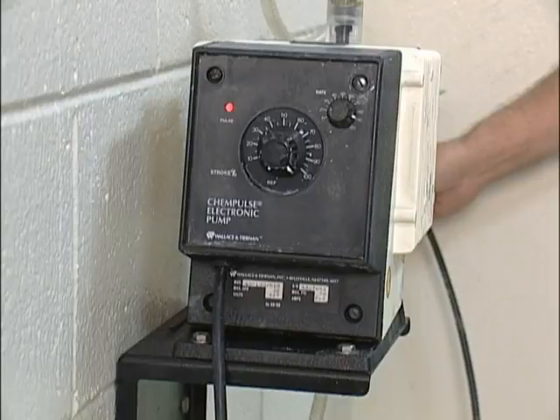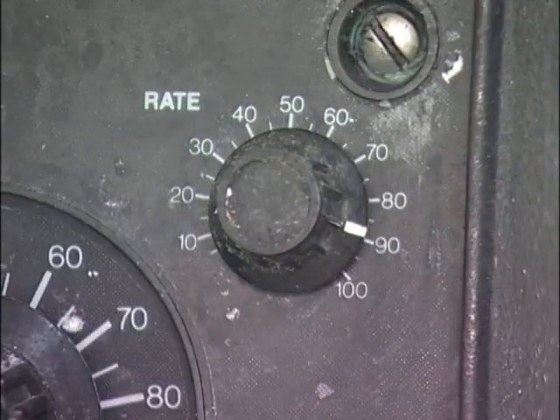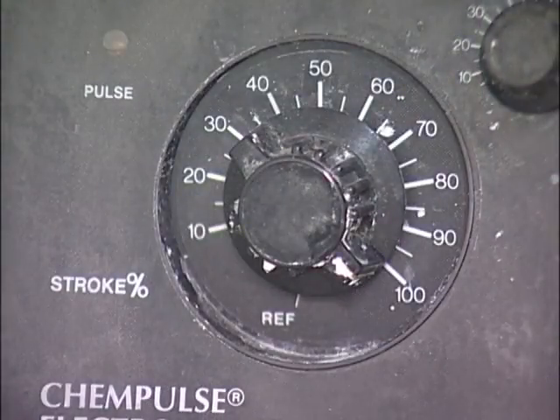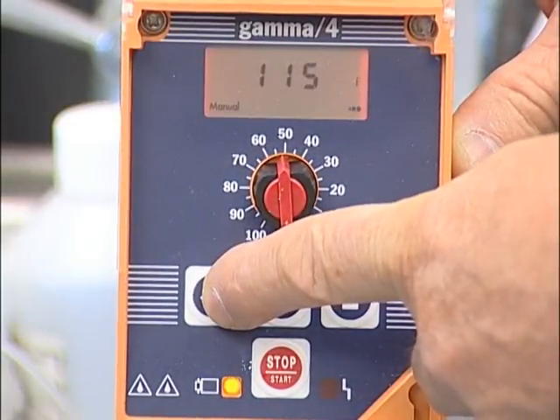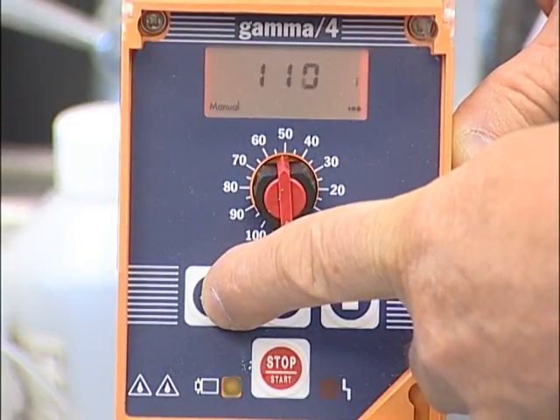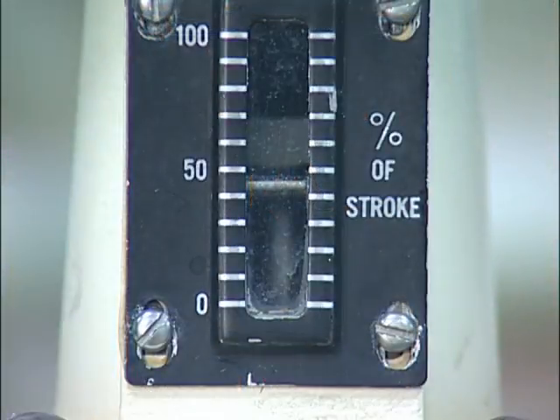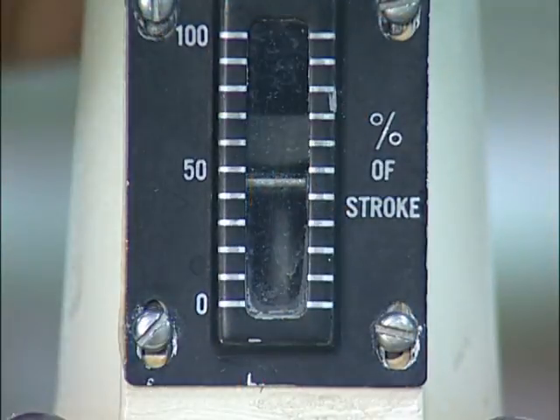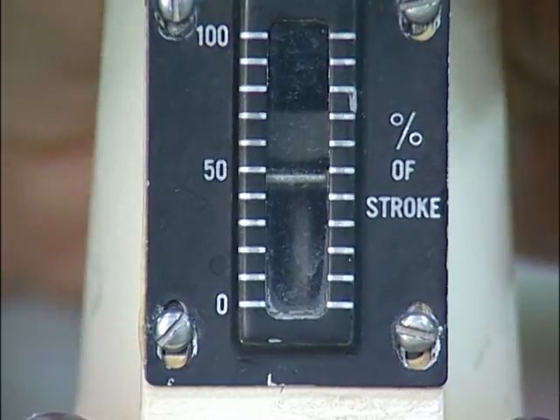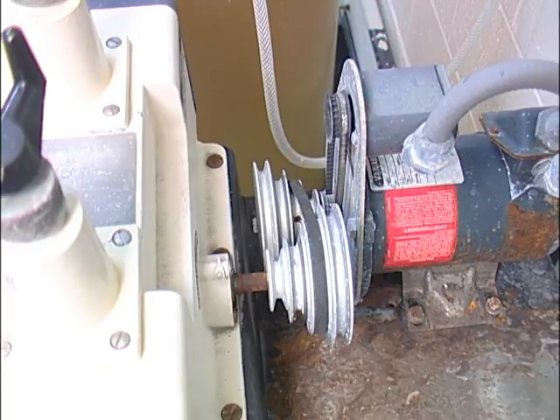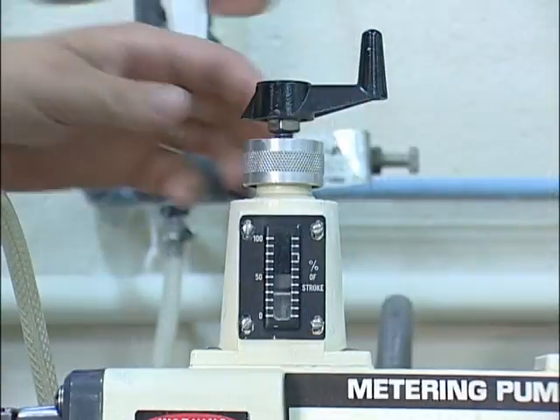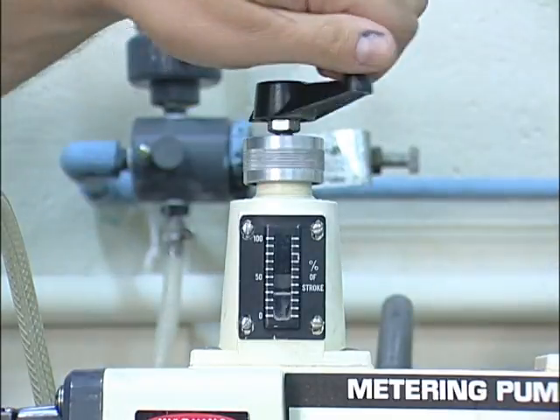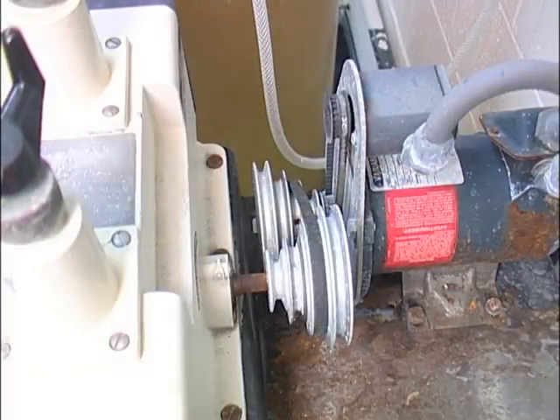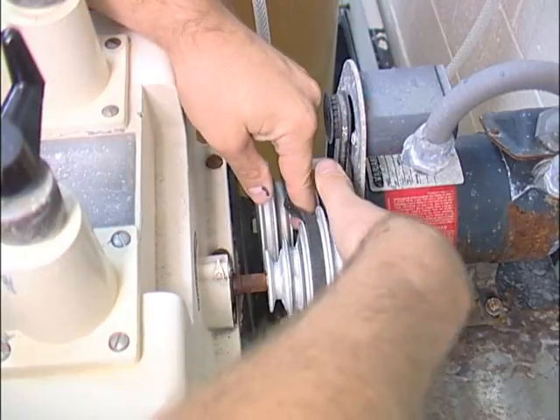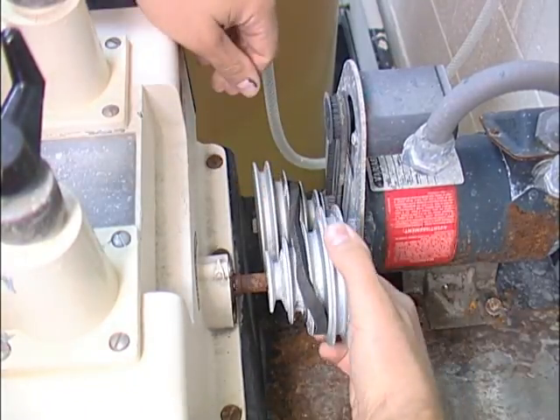Diaphragm pumps frequently have two adjustment options, the speed and the stroke. The speed refers to the frequency of the strokes, or how rapidly the pump will pulse. The stroke refers to the length the plunger will travel in one stroke. The longer the stroke, the more chemical is pumped. Another type of pump uses a motor-driven pulley system. Stroke adjustments are made by turning the crank in either direction, while speed adjustments are made by aligning the different sized pulleys on the pump and the motor.